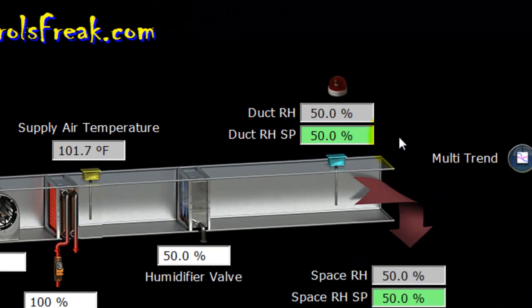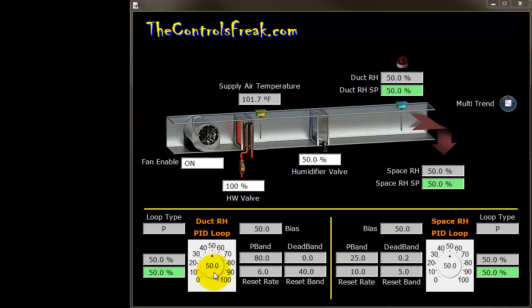The setpoint is shown in this green box — the duct relative humidity setpoint. Based on what it receives on the input compared to the setpoint, it outputs a percentage. That percentage drives the humidifier valve. As your duct humidity moves relative to your setpoint, it adjusts the controller output percentage. In Delta Controls, the PID loop uses a BACnet object called CO — so if you hear me say CO or controller, that's the PID loop, and I'll use those terms interchangeably.